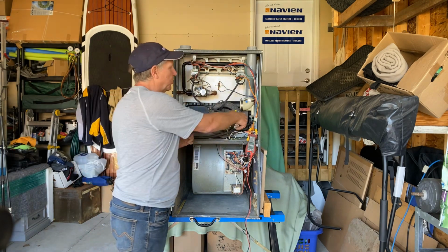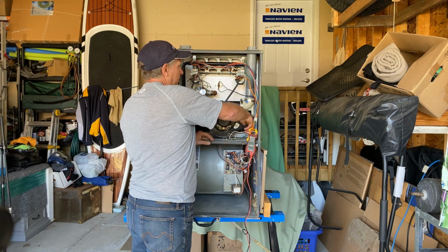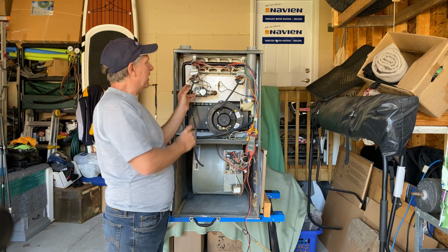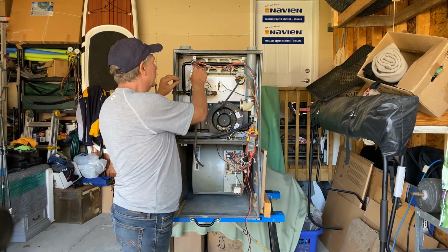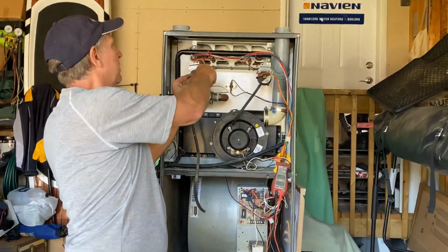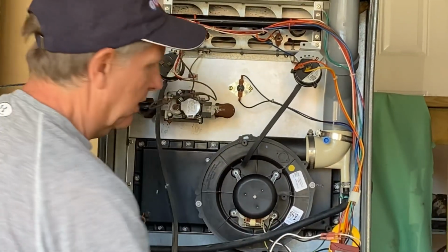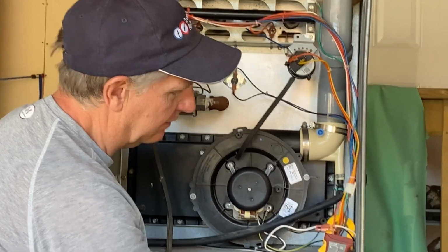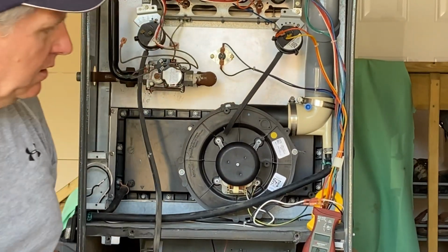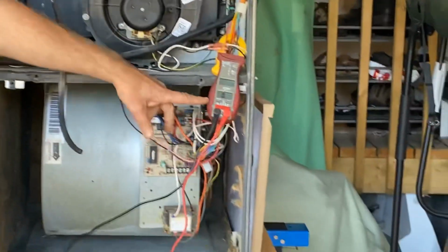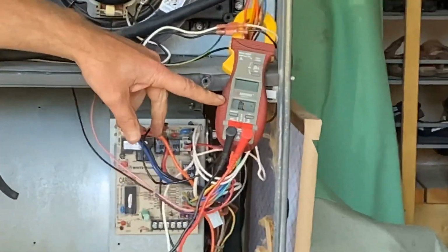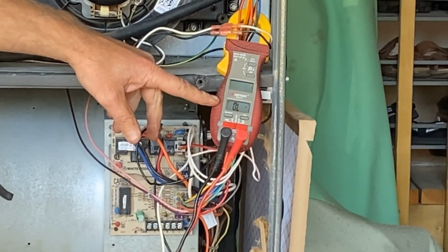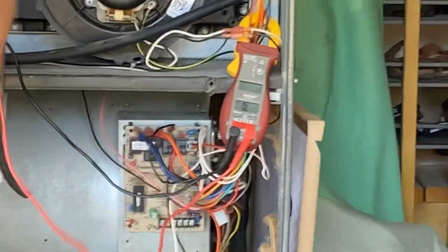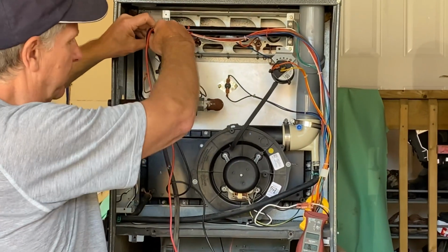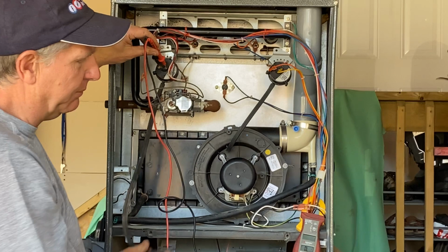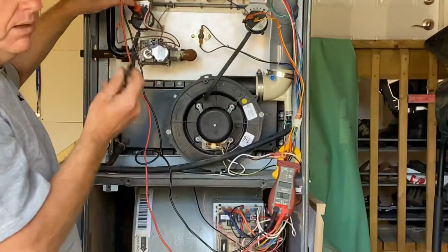So these do sense that. I did want to actually show you one of these in action. I'm not sure if the camera will pick it up. These actually sense negative pressure. Now they don't sense positive pressure, they sense negative pressure. I'm going to pull these wires off. I'm going to turn my meter on here, and I don't know if you can zoom in on that. If you have a look at the meter there, it says OL, open loop. So there's no circuit. I connect my meter to that, I look for continuity. Oh look, no continuity, nothing's happening. If I blow on this, nothing happens.